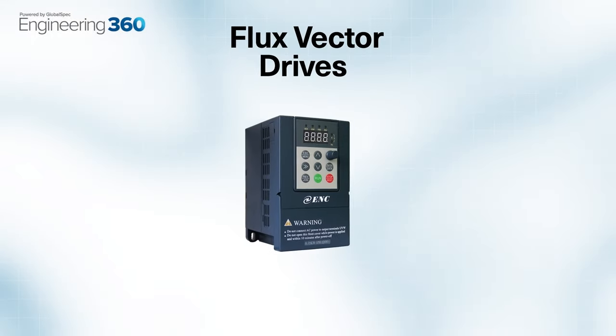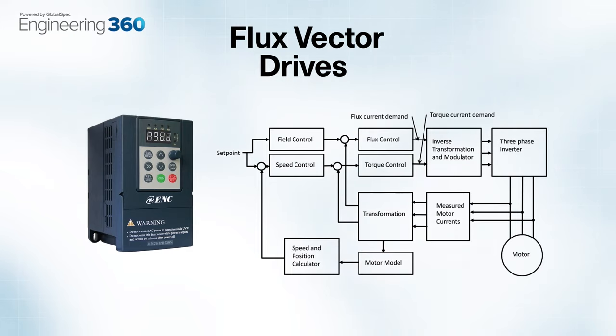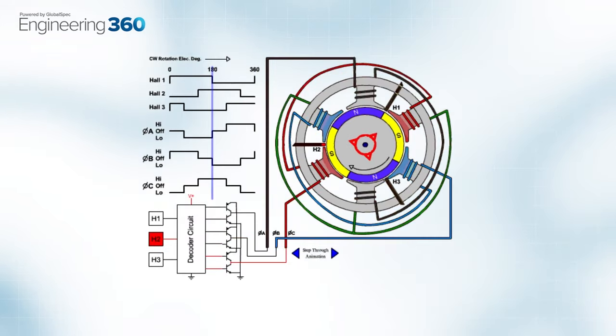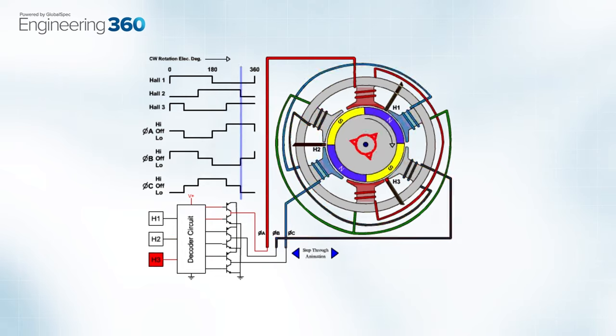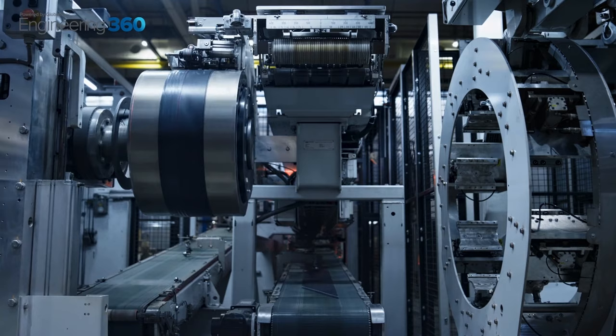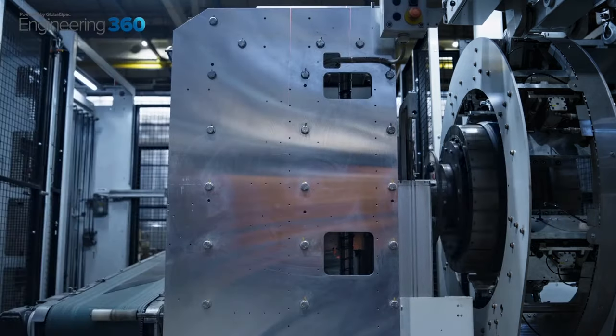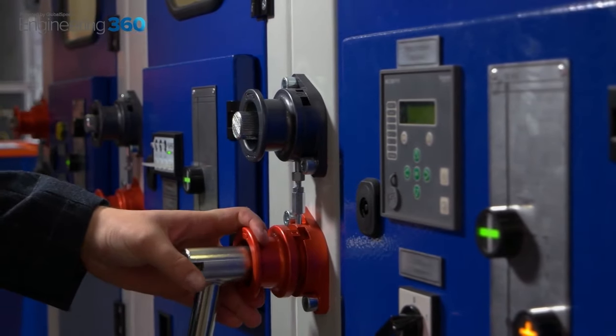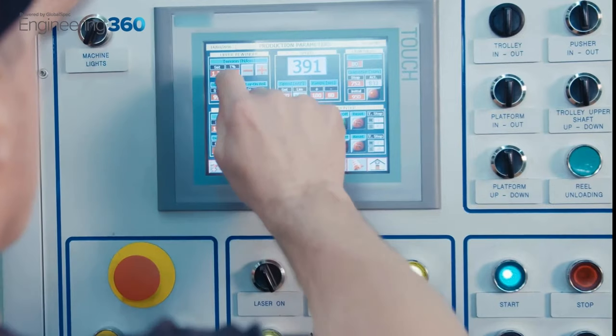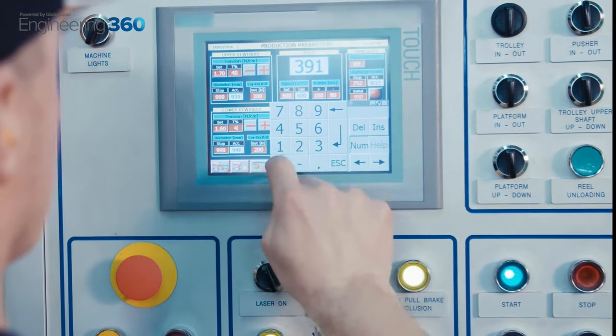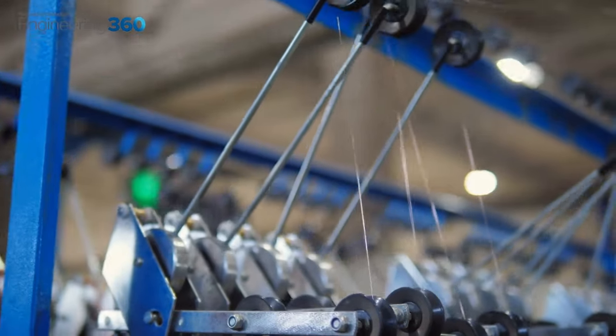The final method of control is using flux vector drives. These drives require microprocessor-based controllers, software, and oftentimes encoded sensors to precisely tune the independent currents. Using this kind of drive enables the operator to control not only the speed of the motor but the torque as well. However, with this increased level of control comes a heavier installation and operating cost.